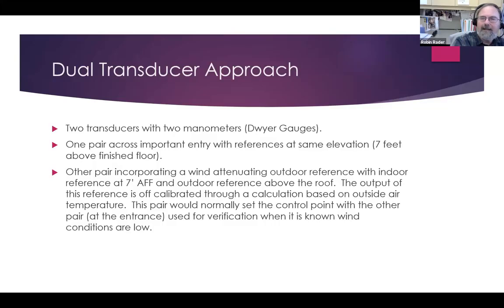Then we also use a wind attenuating head at the top of the building. That transducer is the one that we control off of, and we run the sensor through this stack effect calculation to determine the static pressure. But when there is no wind, then we can look at the manometer across the door, and we can check our calculation and see what the actual building static pressure is.